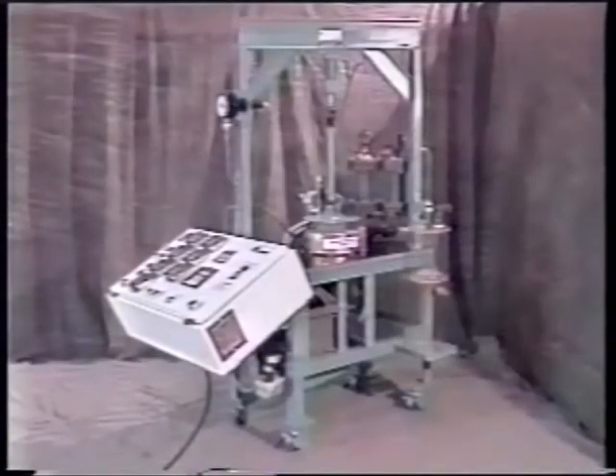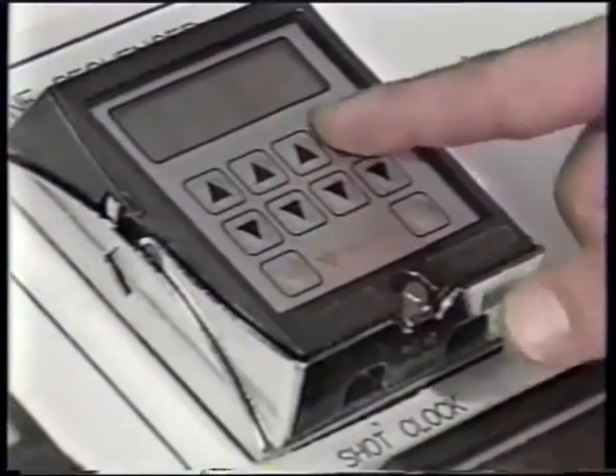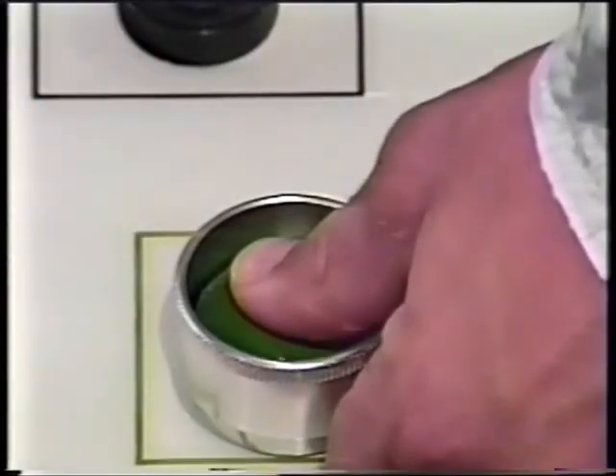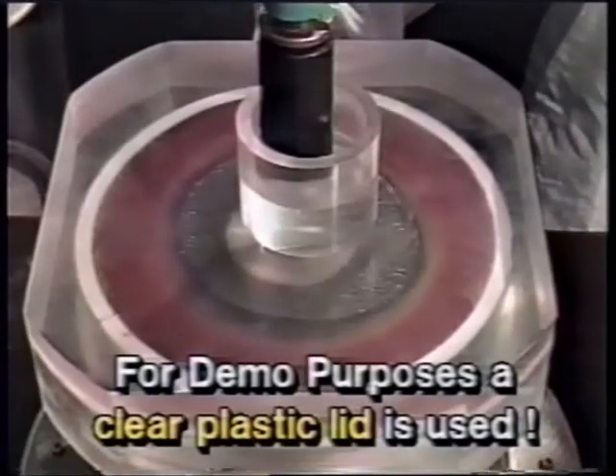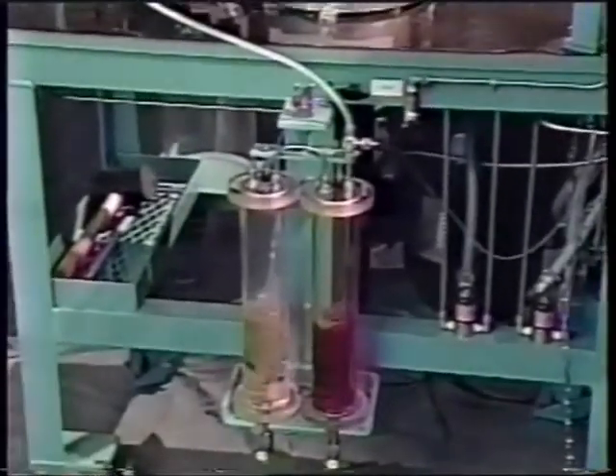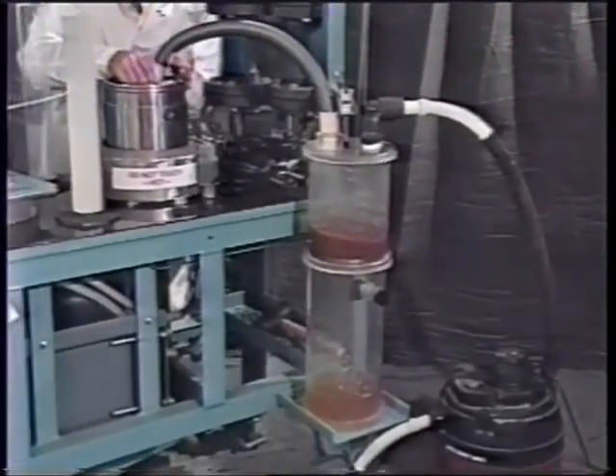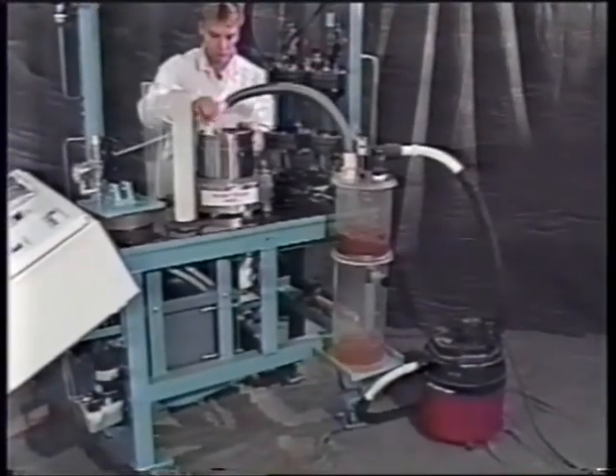Back to the ozone sequencer on the Quantum Mark V — set the mixing speed, mixing time, shot clock reaction time, check pH, and check the temperature. Then hit the start button on the Quantum Mark V mixer. After the timer runs out, the bowl is automatically evacuated. We have deliberately cut the mixing time short to demonstrate how the residual traps work. Remove the lid and extract the pulp using the pulp evacuator. There is still enough ozone left in T1 for two or three more experiments.